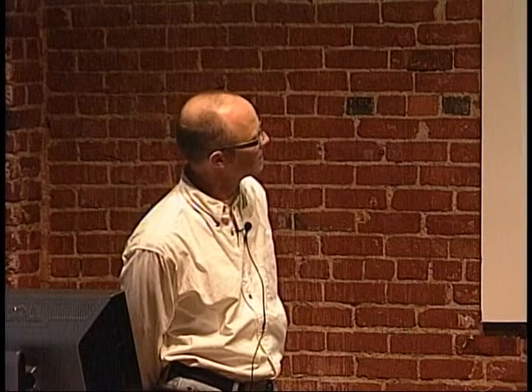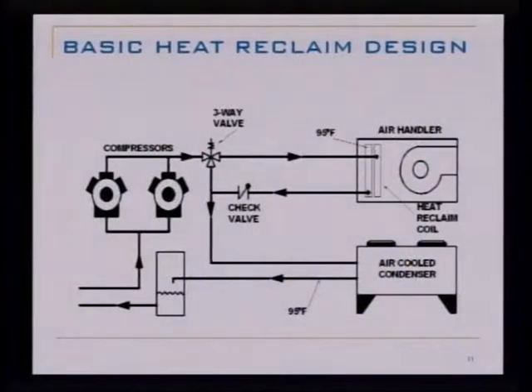Like I say, there's a lot of different ways that this is done. This, I'm arguing, is the most effective way to do it. There's a lot of reasons why it's not universally done. It requires quite a bit more pretty expensive refrigerants. Refrigerants have gotten very expensive and more controlled. And you have to add quite a bit of refrigerant to take into account all of the additional coil and all the additional piping.